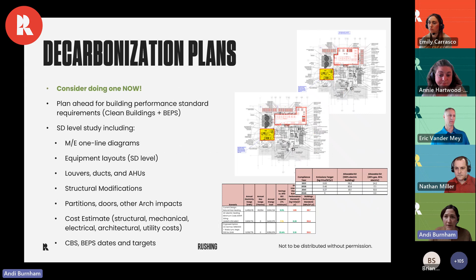As we've been talking about, it's about how we operate that building for the next 50 to 100 years after we build it, and how do we meet our goals as a state so we don't have to go out and build a giant nuclear power plant or some other thing, right? So this is really, what is the cost to run a building in Washington State and how do we mitigate that long term? The energy code can only do so much with existing buildings. So starting in 2026, at the state level, large buildings have to operate to what's called an energy usage intensity target. This is all based on ASHRAE standard 100, and there are very specific rules in place, with penalties now for not operating your building at the acceptable energy usage rates.